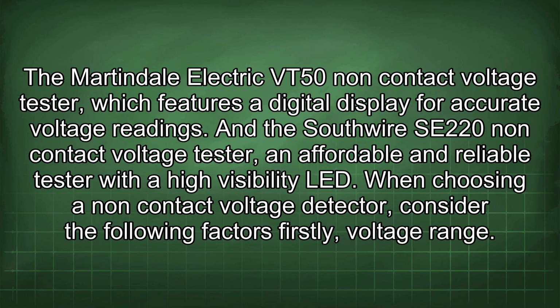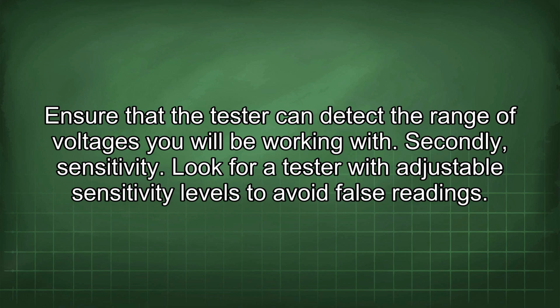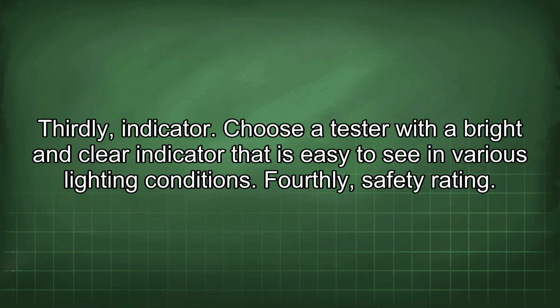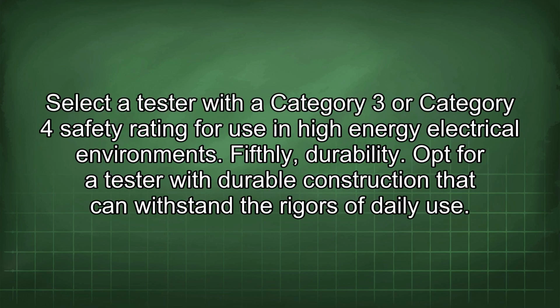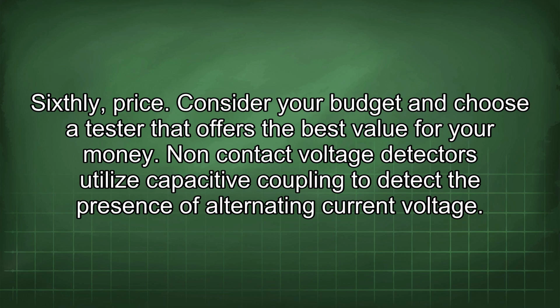When choosing a non-contact voltage detector, consider the following factors. Firstly, voltage range. Ensure that the tester can detect the range of voltages you will be working with. Secondly, sensitivity. Look for a tester with adjustable sensitivity levels to avoid false readings. Thirdly, indicator. Choose a tester with a bright and clear indicator that is easy to see in various lighting conditions. Fourthly, safety rating. Select a tester with a Category 3 or Category 4 safety rating for use in high-energy electrical environments. Fifthly, durability. Opt for a tester with durable construction that can withstand the rigors of daily use. Sixthly, price. Consider your budget and choose a tester that offers the best value for your money.